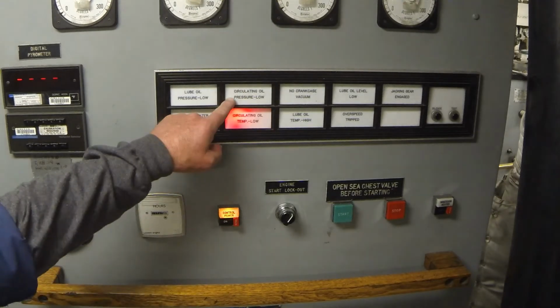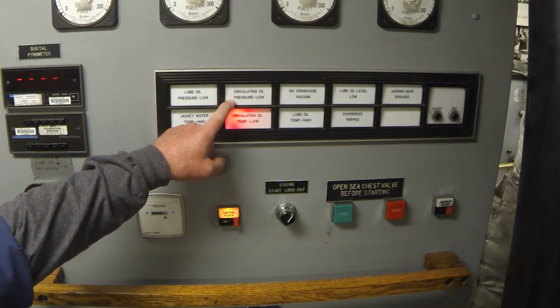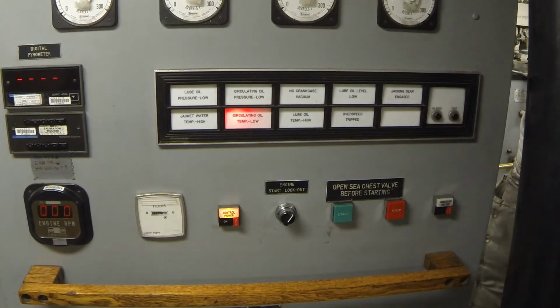But if this light doesn't extinguish, if this alarm doesn't reset, then my circulating oil pump on the lower level could be airbound. There's a little petcock on top of the pump that I could crack open and vent the air off. I do want to use a can though and catch any oil, because if it squirts out, it's going to make a mess.